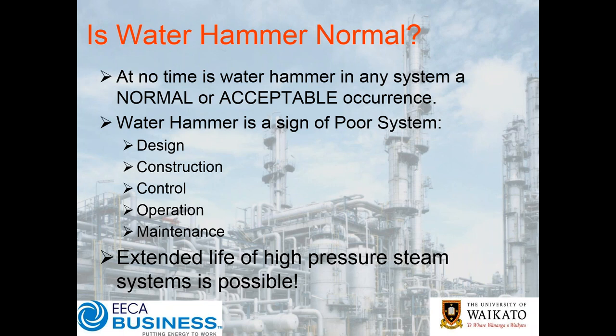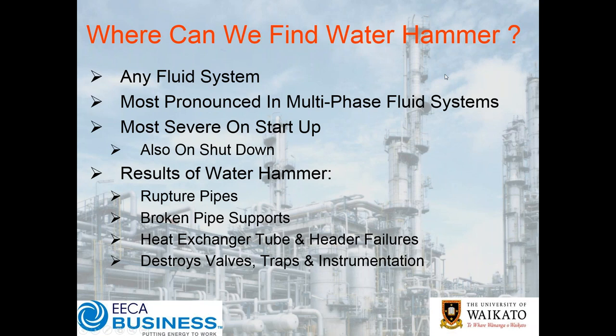It's about acknowledging that this sort of poor performance is not actually acceptable. Where do we find water hammer? Any fluid system. Most pronounced water hammer is in multi-phase fluid systems. Steam is a really good example — where you have both a liquid and a vapor phase, and in steam condensate systems a lot of the time the phases are what we call saturated, meaning the temperature of the stream is at the saturation temperature for the given pressure.